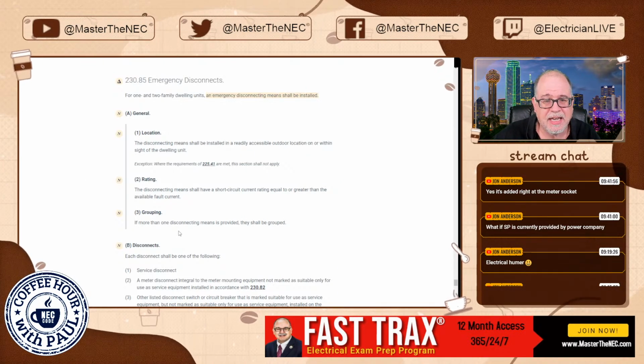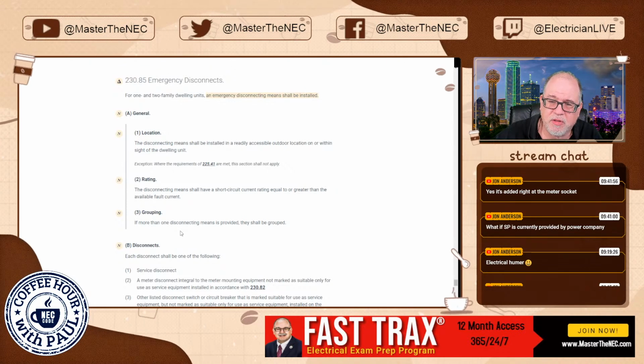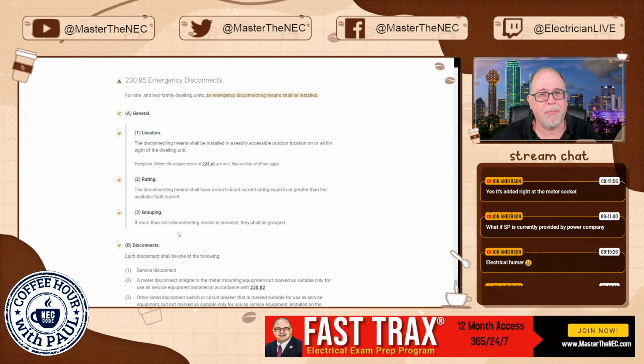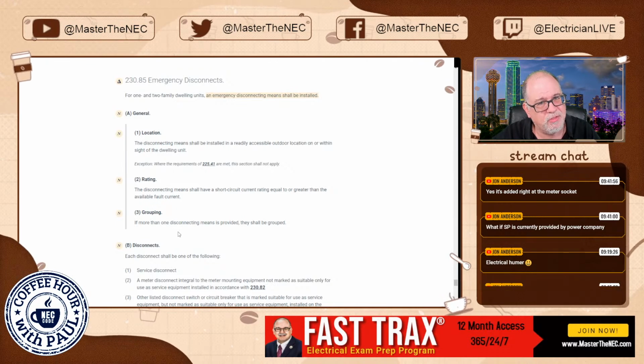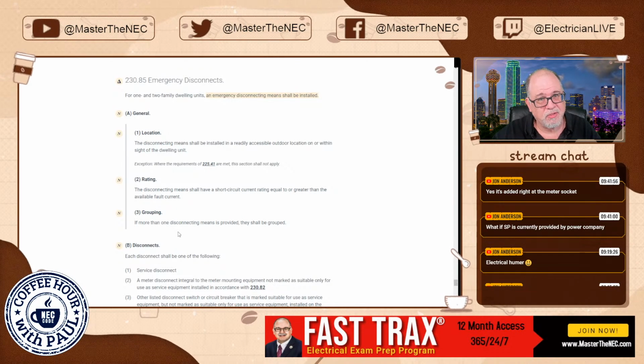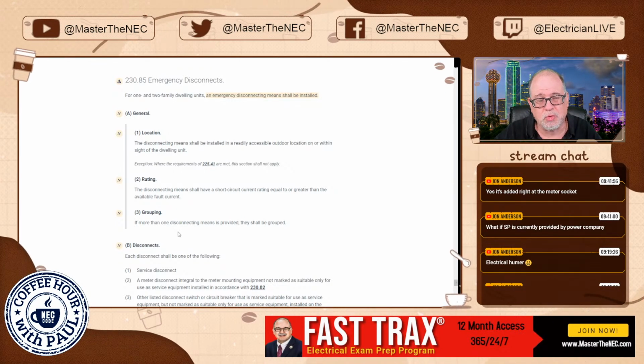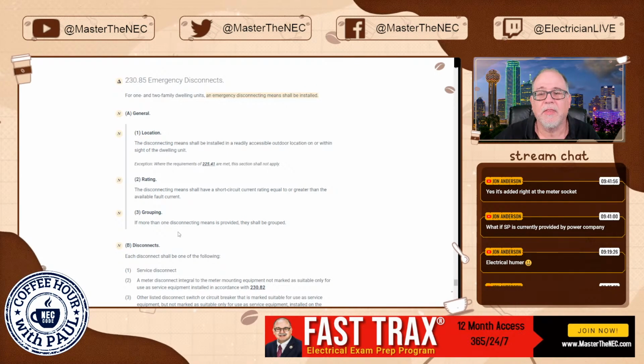Next, the grouping. Again, if more than one disconnecting means is provided, they shall be grouped. And remember that we have the allowances for grouping up to 6, okay, 2 to 6, as long as you meet all those rules. Again, they have to be grouped.